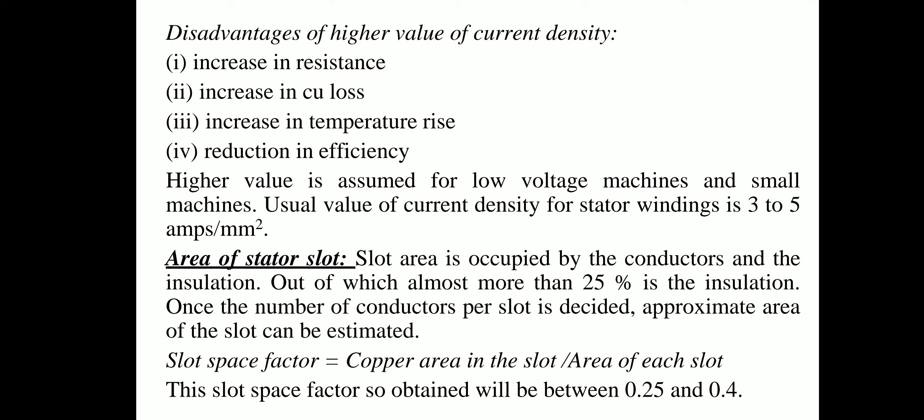The slot area is occupied by conductors and insulation, of which more than 25% is insulation. Once the number of conductors per slot is decided, the approximate area of the slot can be estimated. The slot space factor is defined as the copper area in the slot per total area of each slot, and this factor lies between 0.25 and 0.4.